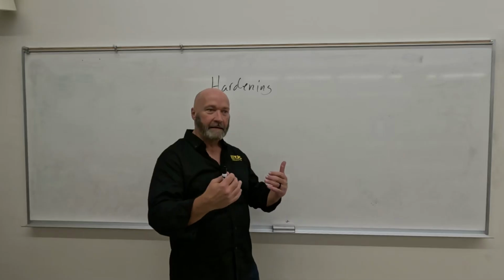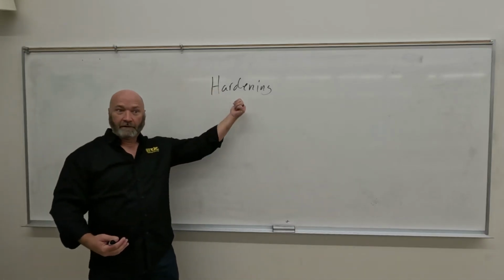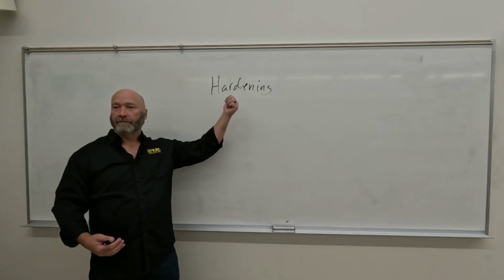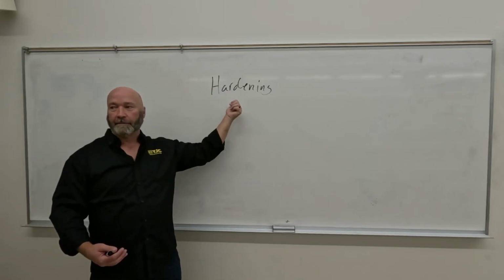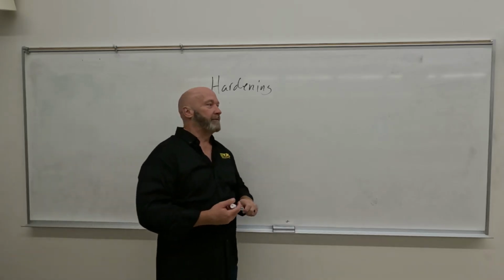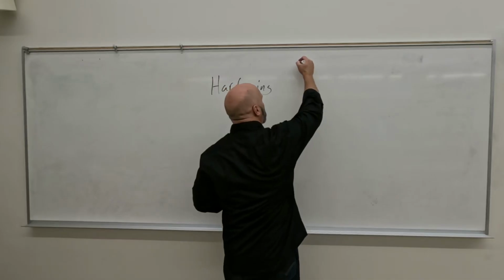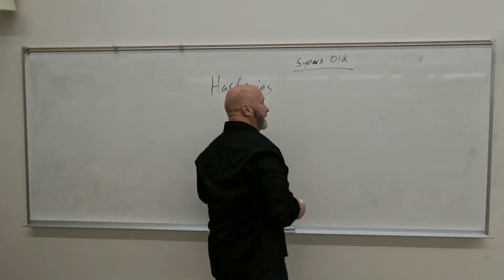So the more tanning you have, the more you're going to lose some of those low energy X-ray photons. You're going to get more filtration, and a harder X-ray beam, okay? So that's the preface. Let's say we've got 2 rooms. One room is 5 years old. What did you create in that X-ray tube over 5 years?